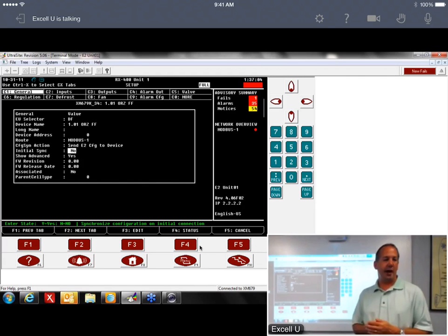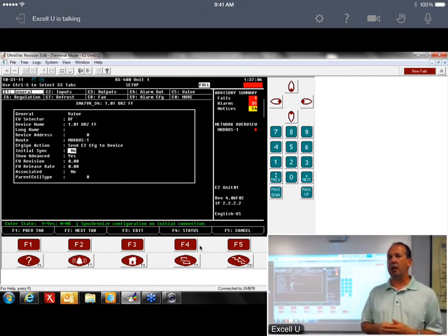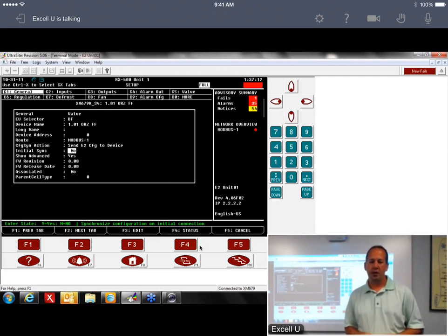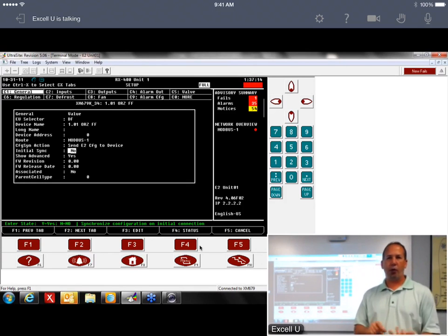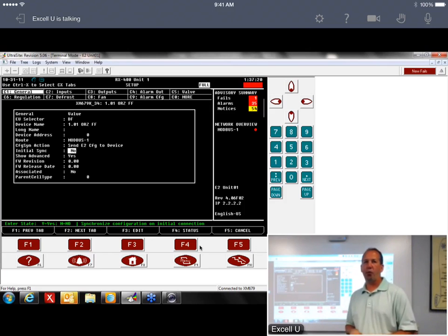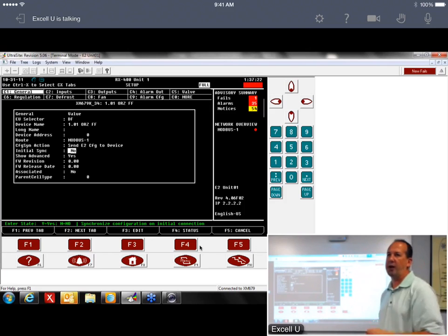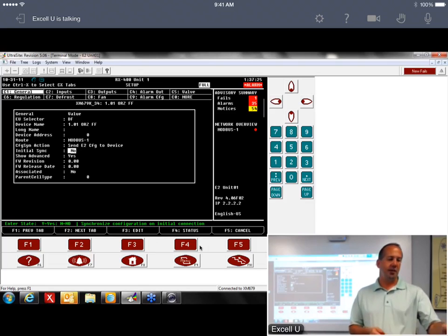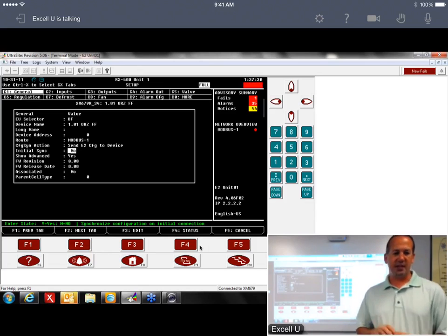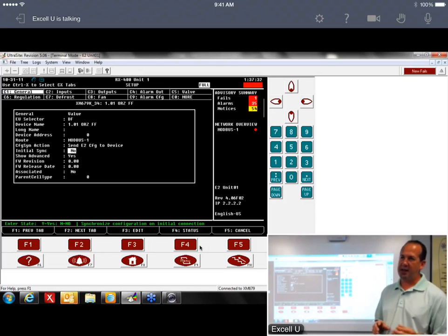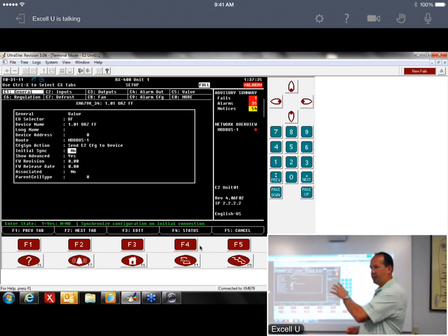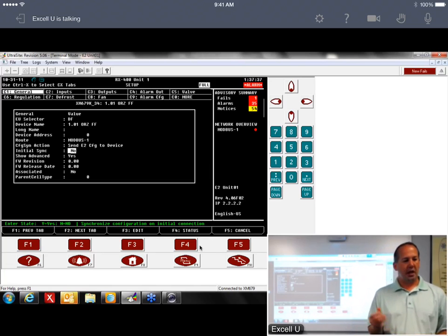If that's set to yes, when you first bring this online, all the parameters that reside in that device are going to dump into the E2. So you go through the E2, program all the XM circuit, the XM device, load it up, and if you forgot one parameter, all your work's for nothing. It's going to overwrite it all, and it's going to have all the settings in the E2 that were in the XM device that don't work. So then you've got to reprogram the thing. So initial sync has to be set to no, and that will eliminate that feeding into here. The reason it's set up that way is it's for a hotkey.